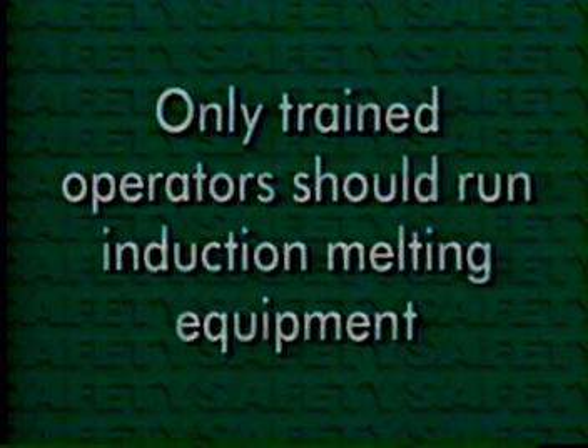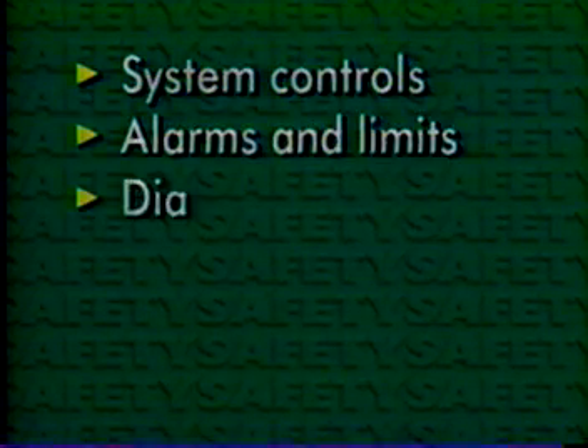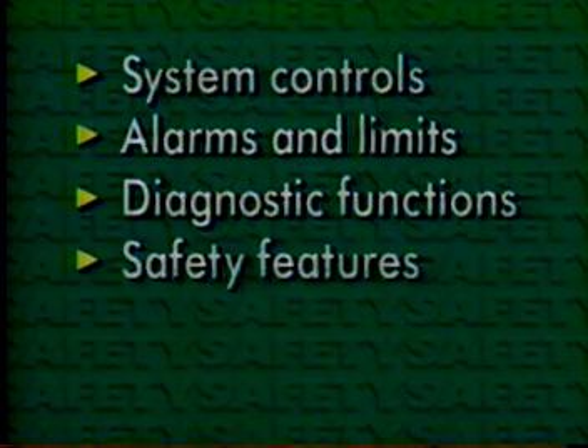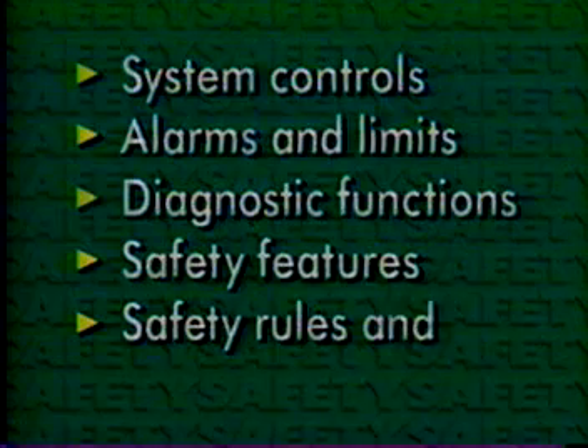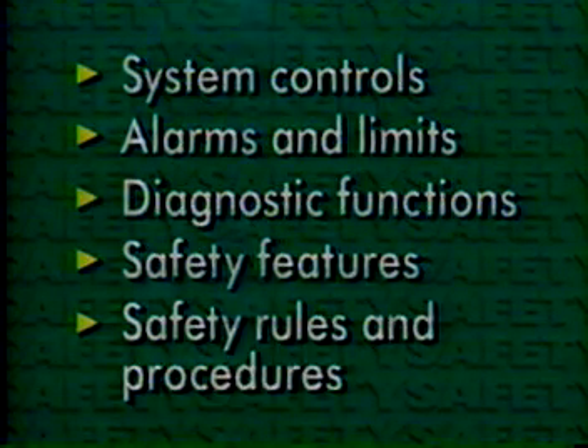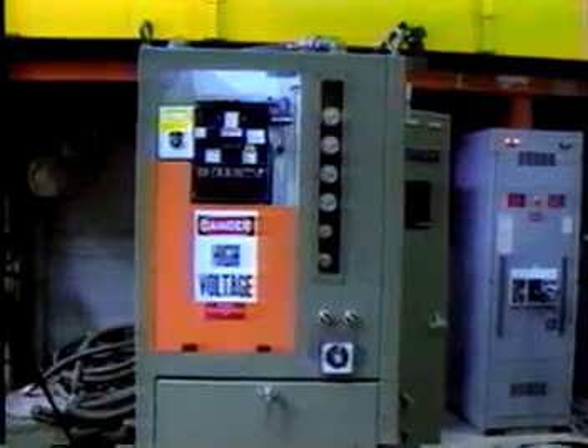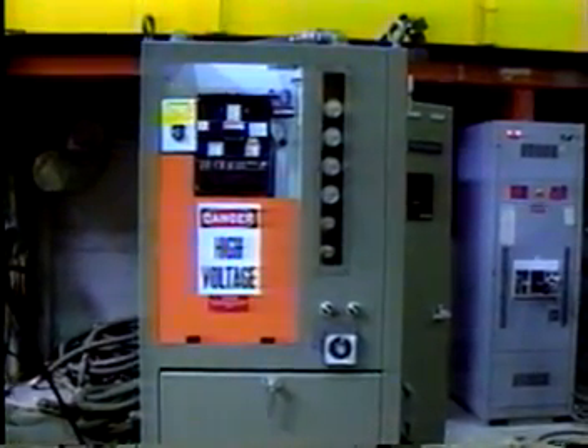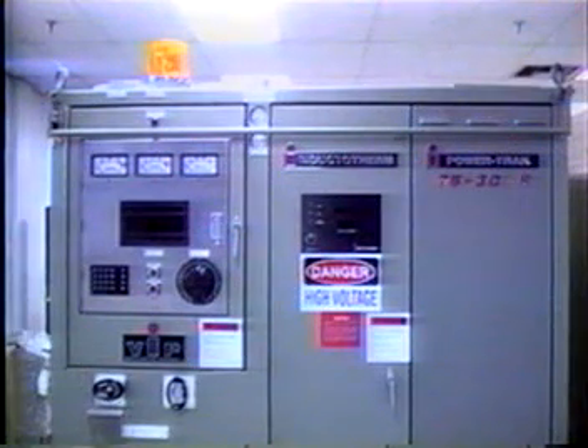The first rule is that only trained induction system operators should be permitted to run induction melting equipment. A trained operator must be fully knowledgeable about the system's controls, alarms and limits, diagnostic functions, and safety features. He must be fully versed in the safety rules and procedures related to the system's operation. To keep all personnel alert to the dangers associated with induction electrical systems, warning notices must be posted on all equipment that operates at high voltages, and these notices must not be removed or covered. All power supply doors and lockable protective enclosures must be kept locked and the keys secured and controlled.